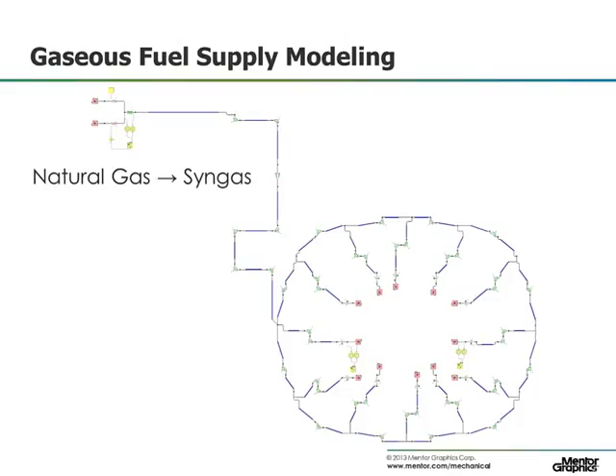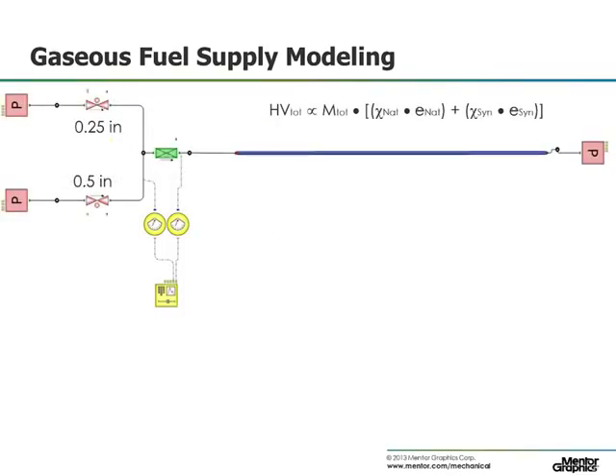Before, we looked at the basics of Flowmaster's fluid mixing capabilities, but with this model, we will go one step further and measure fluid concentration, and use the result to develop a closed-loop feedback fuel control system. One of the many challenges to overcome in a fuel switching scenario is that of fuel energy density. Because syngas typically has a lower energy content by volume than natural gas, the switch from one fuel to the other must be done carefully and in a controlled manner to ensure that turbine power is not affected.